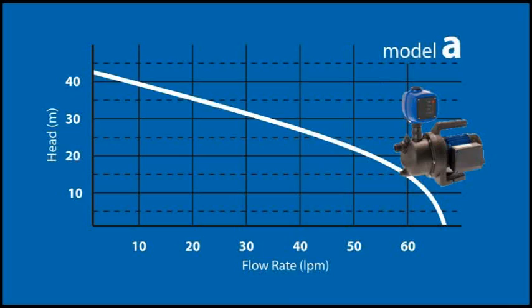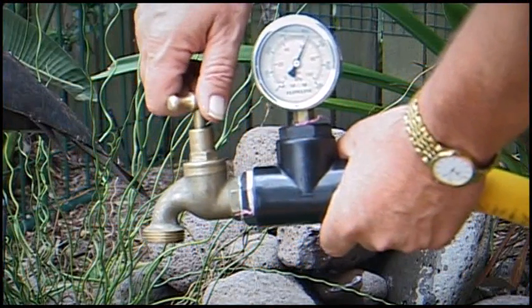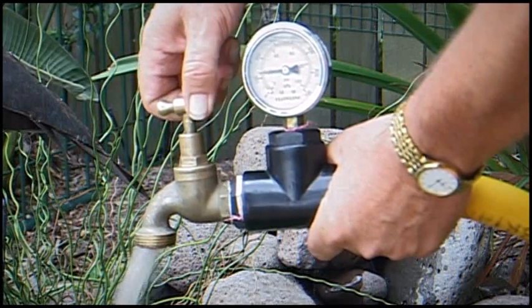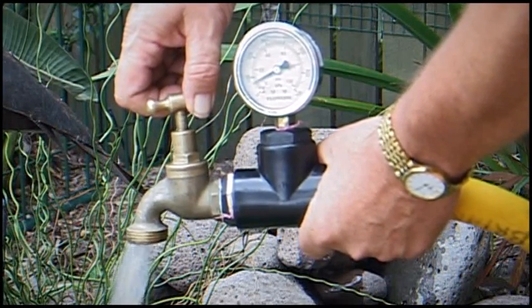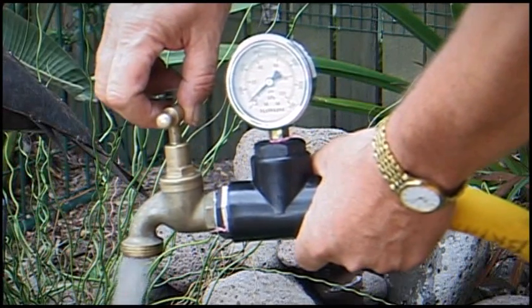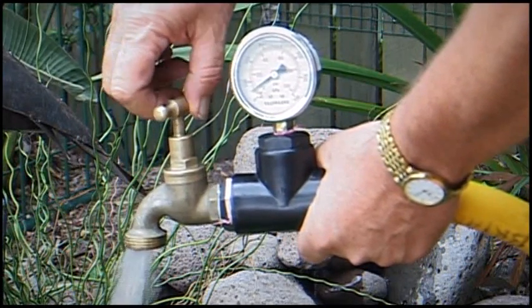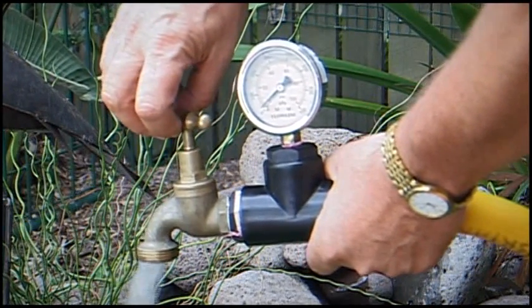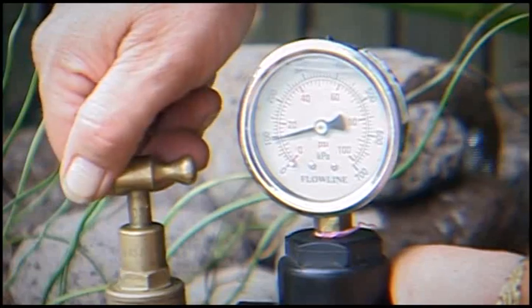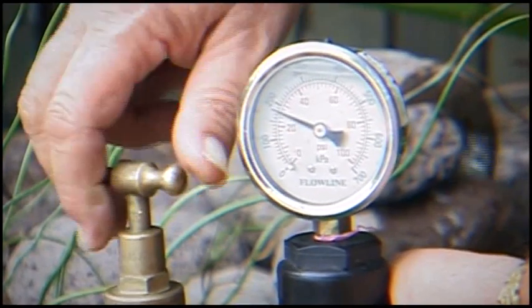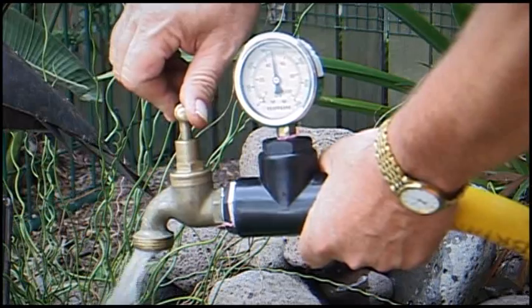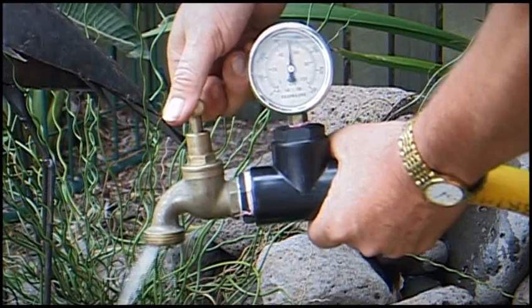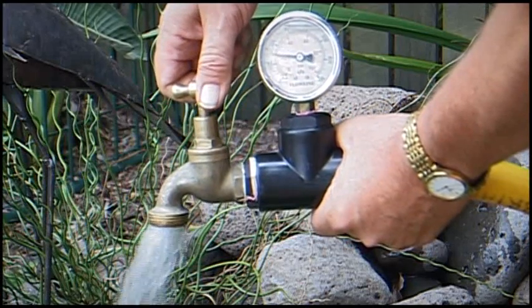As you can see, pressure will always affect the flow. Another way we can show this is by putting a pressure gauge with a tap on a hose and connecting it to a pump. When we open the tap completely, the flow increases as the pump is not working against pressure. Watch what happens as we increase the pressure the pump has to work against by slowly closing the tap. The flow rate is reduced. Let's remove some of the pressure and watch as the flow rate increases.